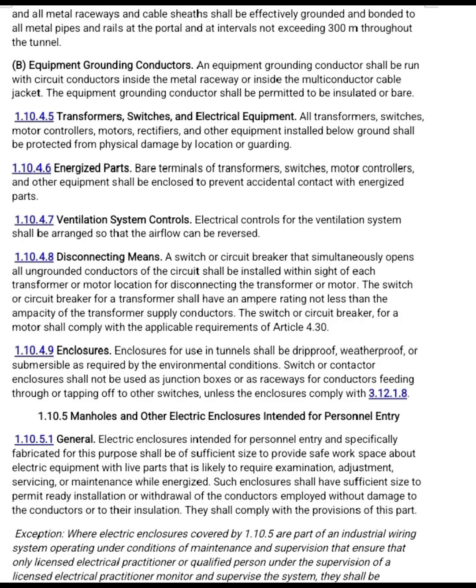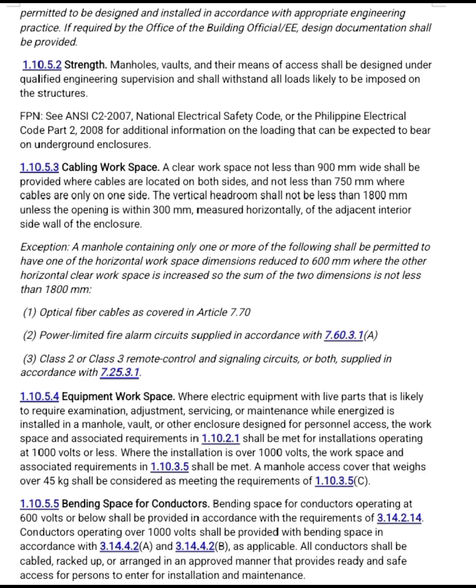1.10.5 Manholes and electrical enclosures for personnel entry must be made strong and safe for workers, provide enough space to work safely around live parts, and follow all safety rules in this section. Permitted to be designed and installed in accordance with appropriate engineering practice. If required by the office of the building official, design documentation shall be provided. 1.10.5.2 Strength. Manholes, vaults, and their means of access shall be designed under qualified engineering supervision and shall withstand all loads likely to be imposed on the structures.